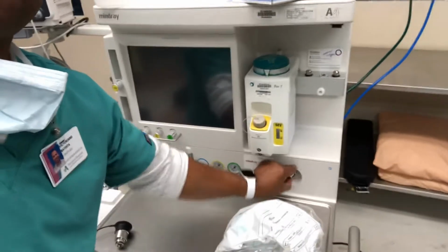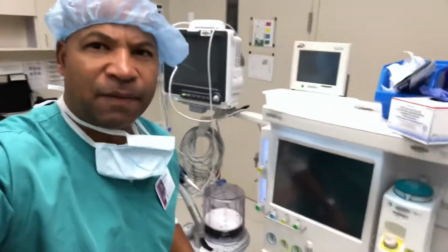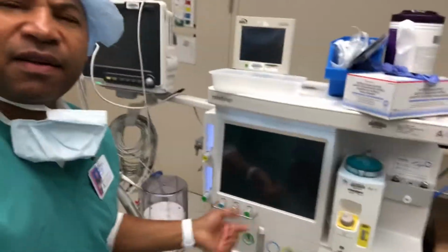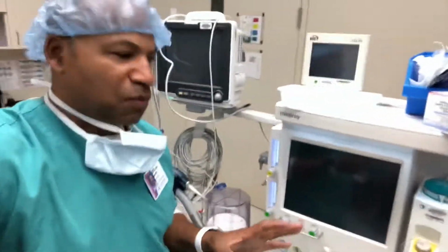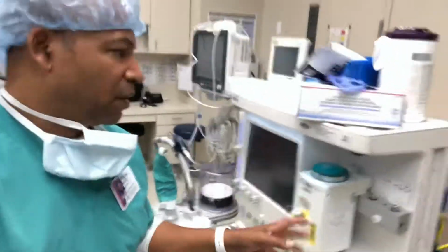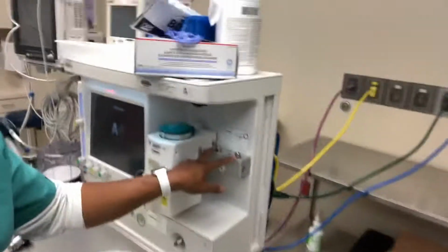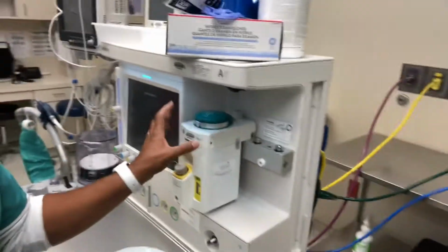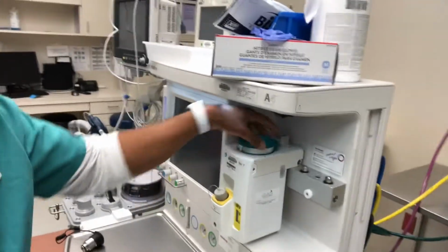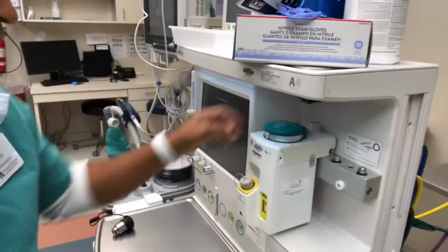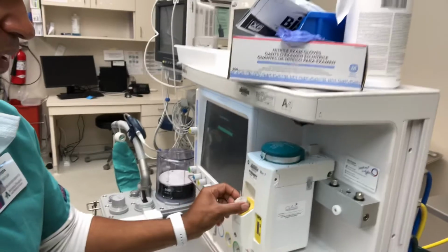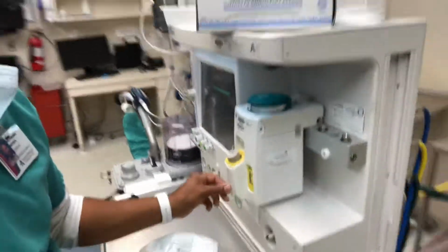So we're going to go ahead and just power it on over here. And once we get the unit powered on, we're going to look at the display again and make sure that our volumes, everything is accurate. We have our O-rings here for the vaporizers. Check to see that the cap on the vaporizer locks into place. Everything is nice and tight. We don't want any leaks anywhere.